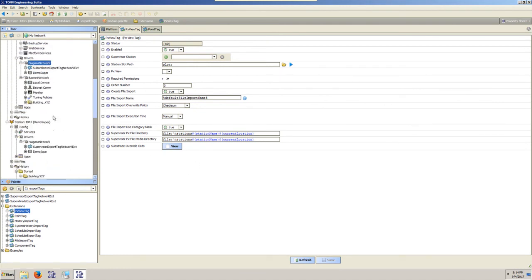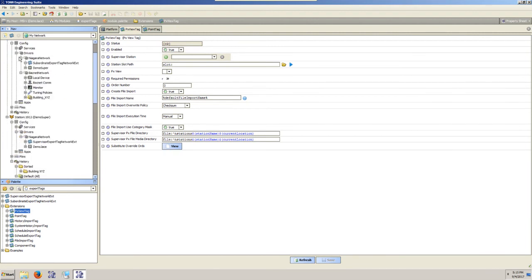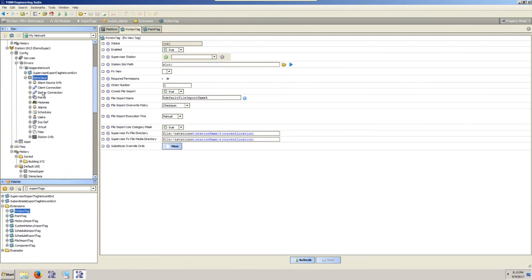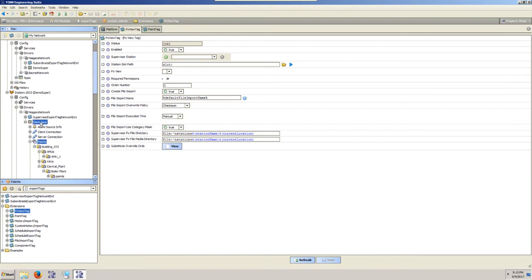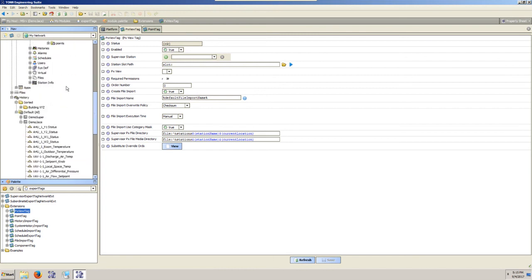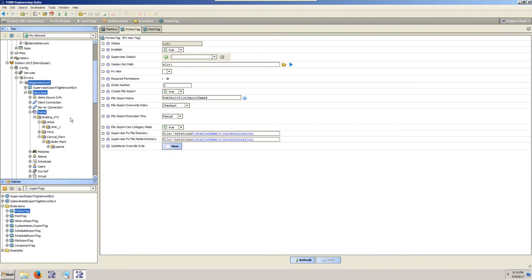To copy your graphics, if you did have graphics already set up in the jace, your biggest difference is, instead of all your points being under, let's say, the BACnet network and then wherever they're going to be, they're now under the Niagara network and the jace name. So basically, you're typically doing a find replace for BACnet network and just changing it for Niagara network, jace, and then you're in the points/points. So you might be looking for those 3 items, doing a find replace on your PX files, which if you do that in text mode, just edit your PX, go and view it as a text file, do the find replace. It's pretty quick and easy to take your graphics and move them to the supervisor.